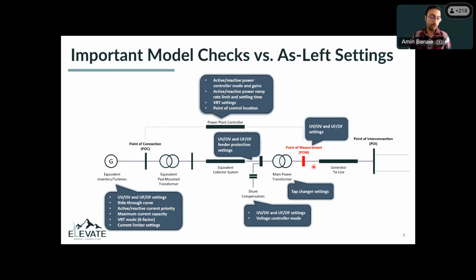Now, going to the inverters, some other items that you can check to make sure they match what's in the field can be the ride-through curves of the inverters, the LVRT curve and HVRT curve, the active and reactive current priority, the maximum current capacity, Imax, of the inverter, the VRT mode, whether they're following K-factor or some other control strategy, and any information about the current limiter setting, because that's going to determine how much reactive current or active current is curtailed, and it's going to impact the evaluation of requirements R2.1 and R2.2 in PRC-29.